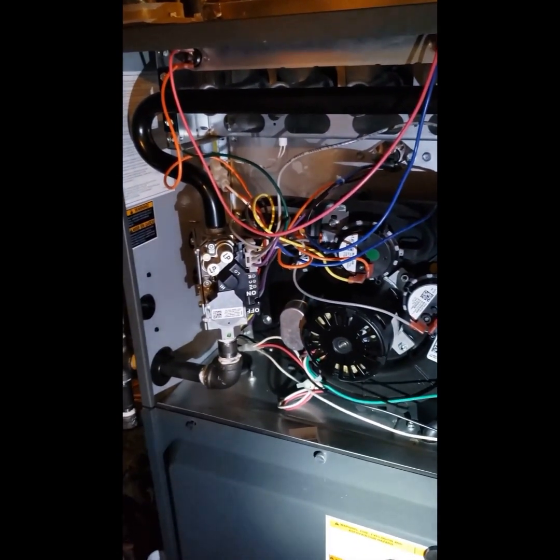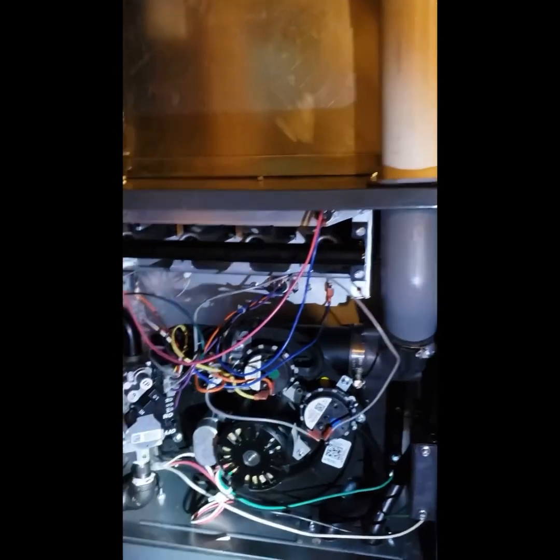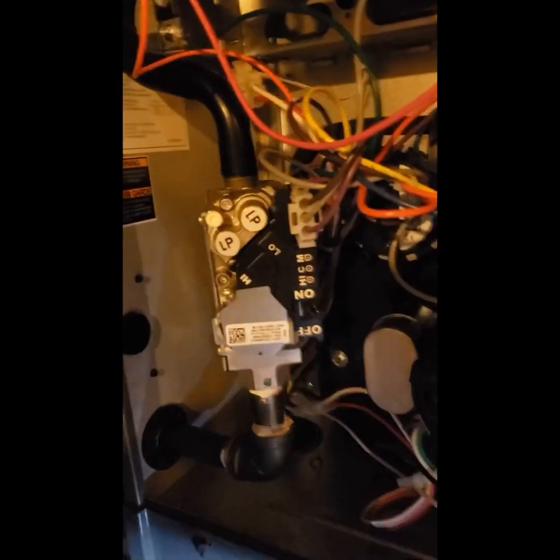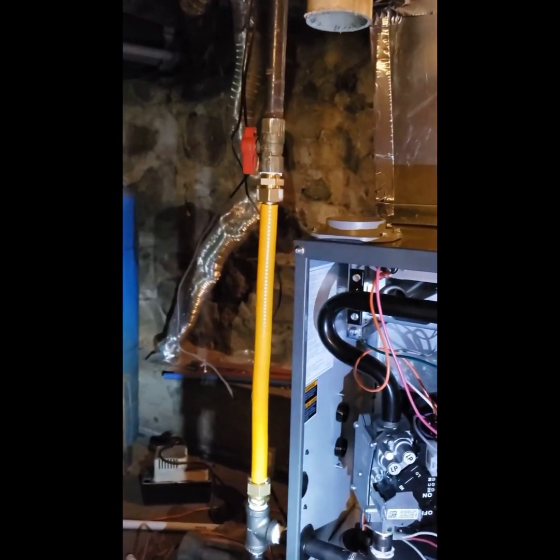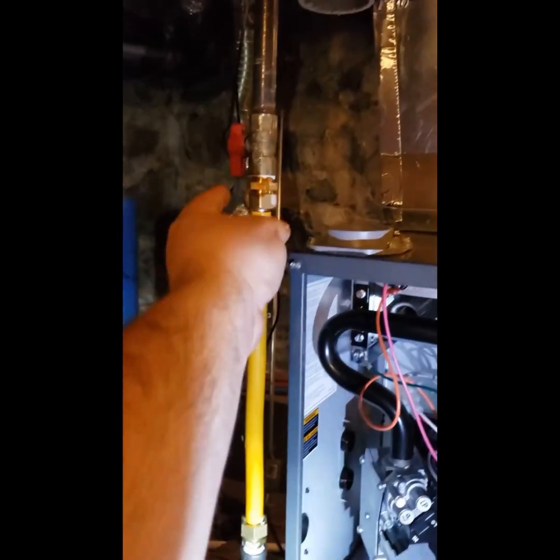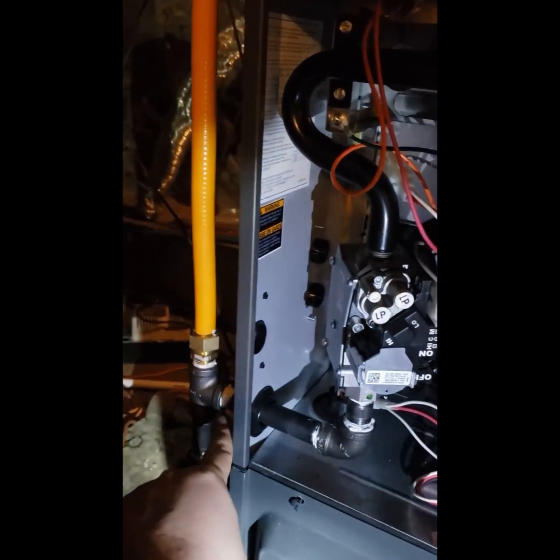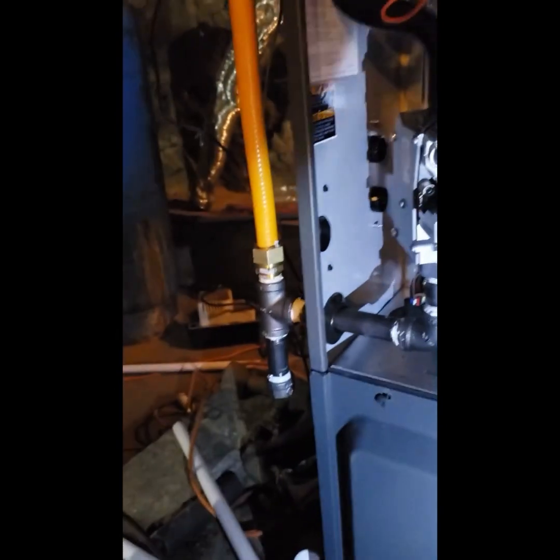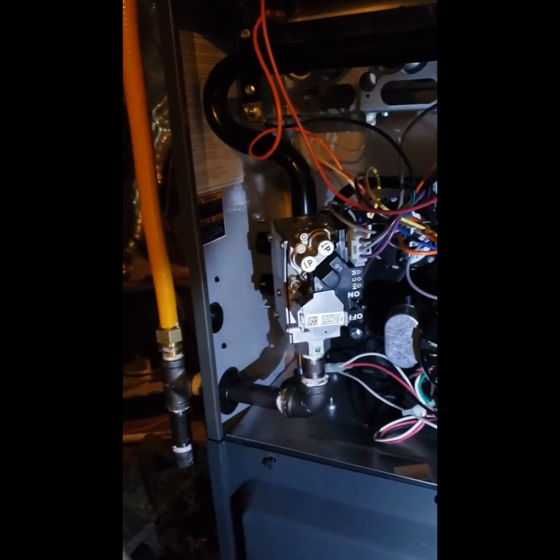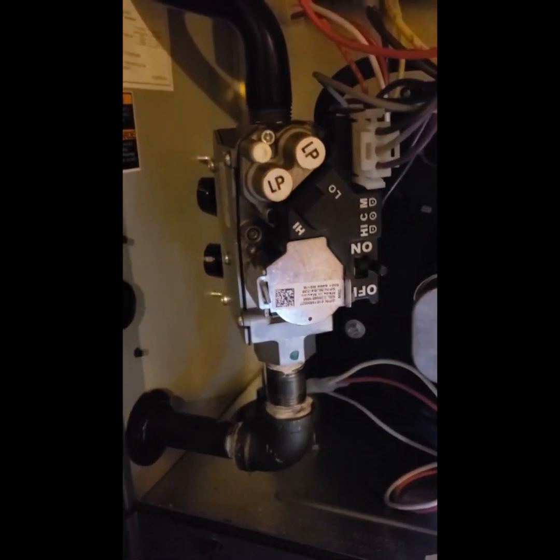This is a two-stage high efficiency Goodman furnace — I know it's two-stage because down here on the gas valve it says high and low. I'm in the middle of this installation and I wanted to show you gas pressure. Here's my gas shutoff, I have a piece of CSST tubing coming down, a drip leg, going into the furnace and up into the gas valve. This happens to be a White Rodgers gas valve, and this furnace has been converted to LP.